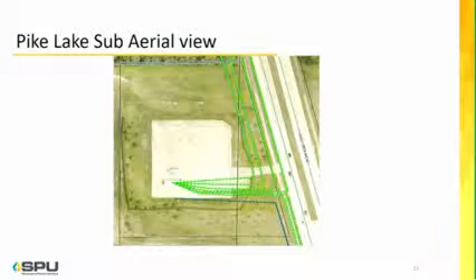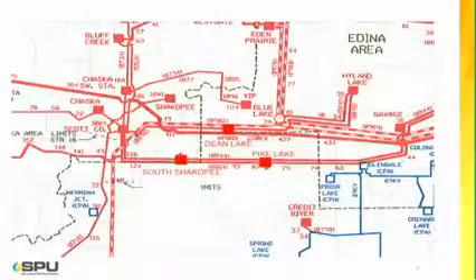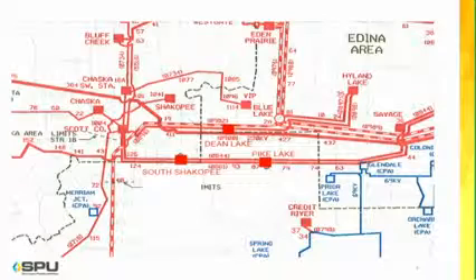Here's the east-west transmission line, going back to the transmission map. So this is the Pike Lake sub. We have double circuit on wooden structures running east and west across the southern part of the system. The Pike Lake sub taps one of those 2 circuits, and South Shakopee taps the other. That was by design, again for higher reliability, so should there be an outage to either line for whatever reason, it wouldn't impact the other sub at all.